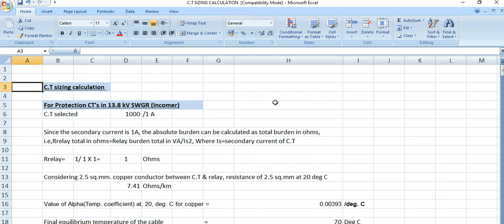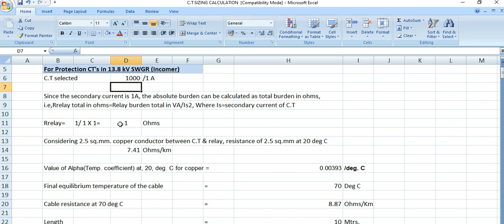In the first part, I will discuss the protection CT sizing calculation. In this project, we have 13.8kV switchgear — this is for a 13.8kV incoming feeder — and the CT ratio is 1000 by 1 ampere. Now we have to calculate the CT burden.